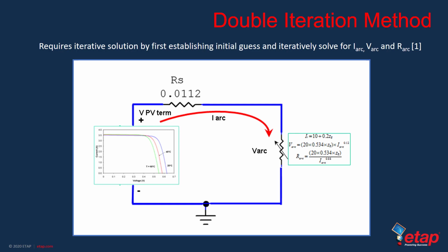To summarize this slide, we can see that the stability point of the arc resistance and current can only be established by a set of multiple iterations on both the IV curves and the nonlinear Stokes and Oppenlander arc current and gap conditions. In other words, both the arc resistance and current have to be solved iteratively, and at the same time we must determine where this arc stabilization point lies on the IV or short circuit curve characteristics of our panels.